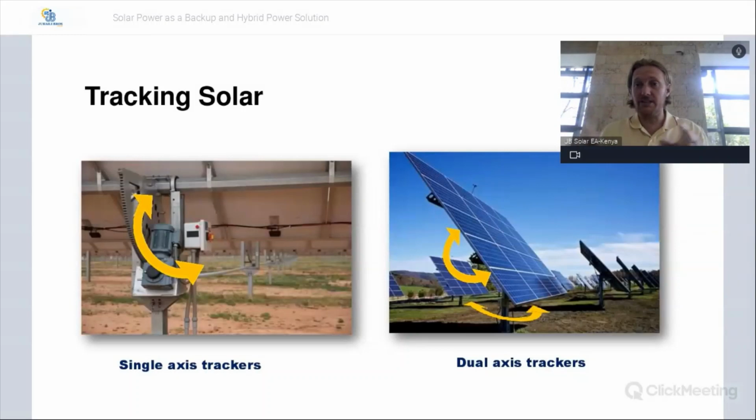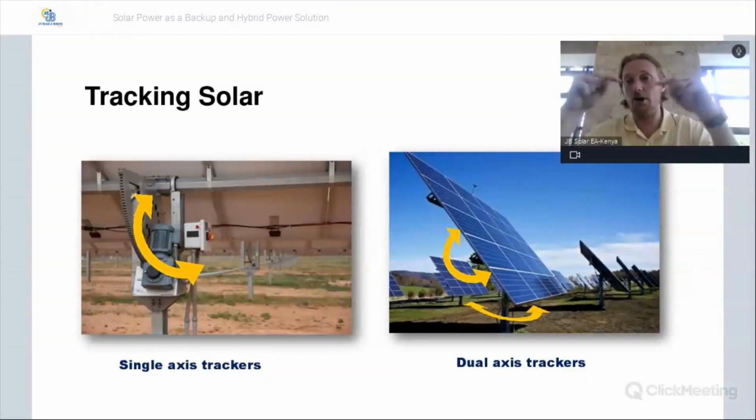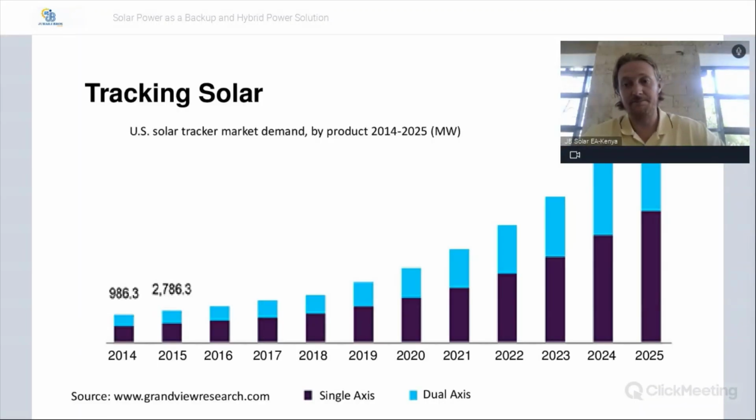If you look at the globe and look at the land mass anywhere in the world, for 91% of the Earth, solar panels with single axis trackers are the cheapest and most efficient power available on Earth. Dual axis trackers only make financial sense way in the north and way in the south, near and above the Arctic Circle. That's the only place where the additional yield matches the costs. For the rest of the planet, single axis trackers are the best choice.